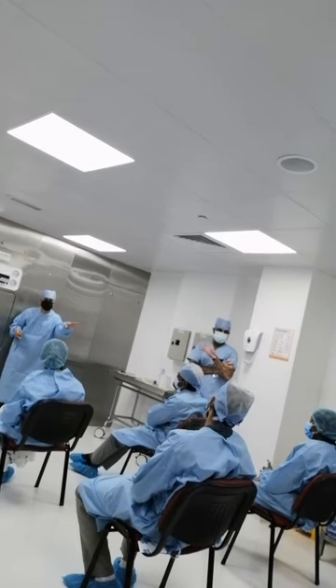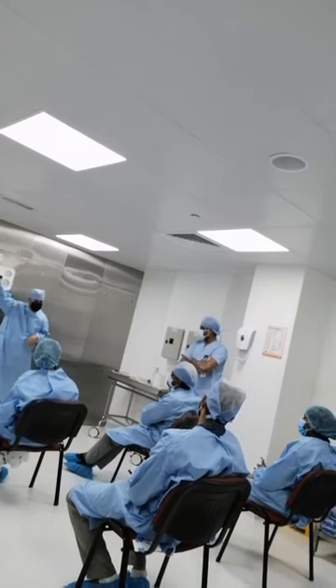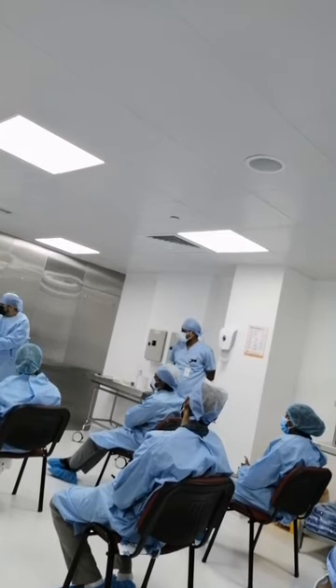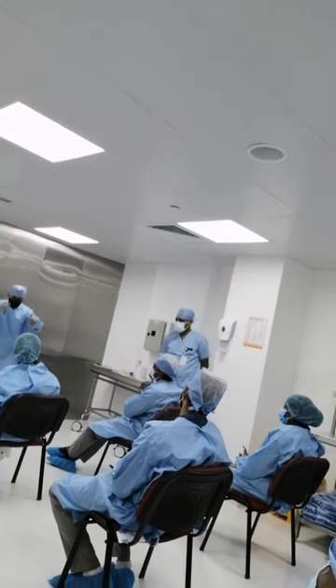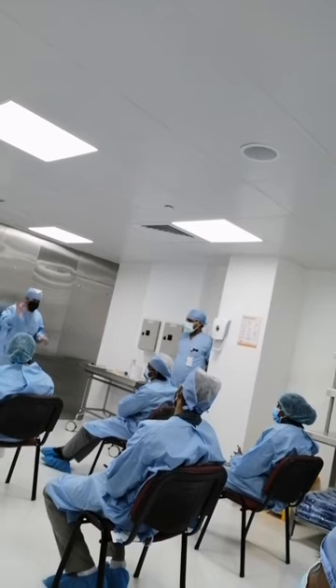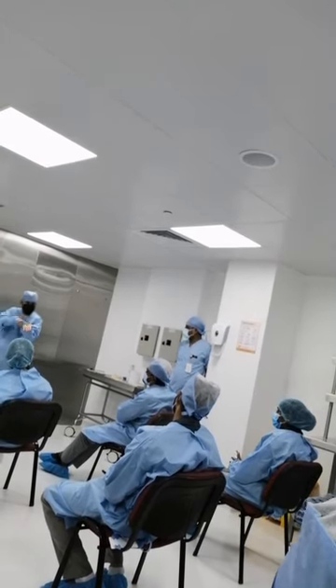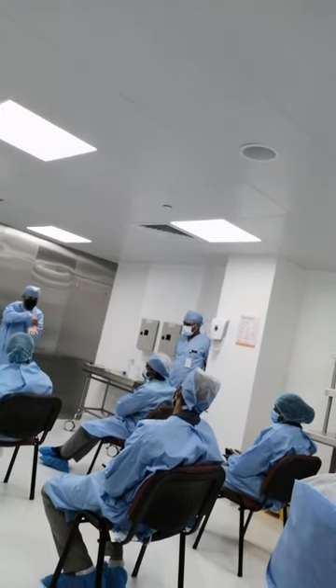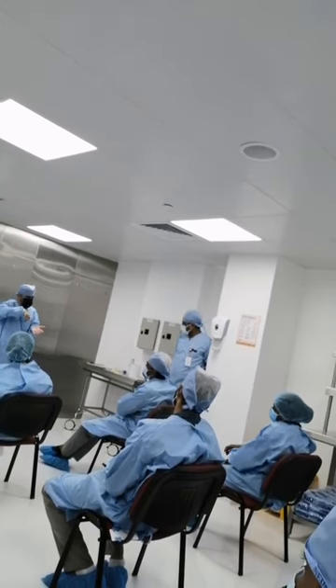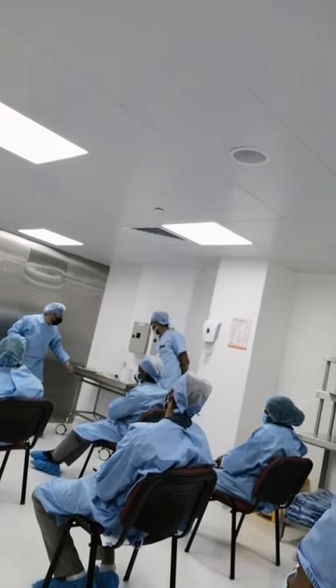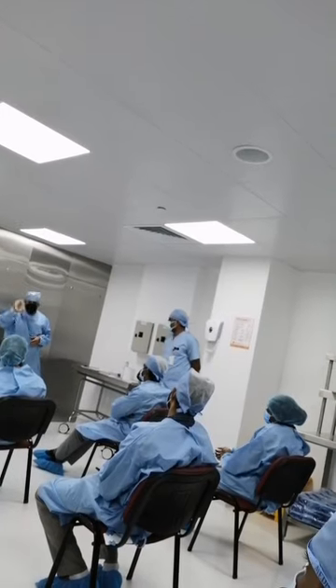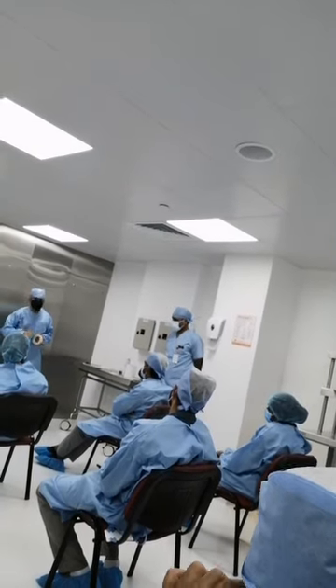If you find it in the Middle East, you will find somebody from the oil and gas section, and they will come and put some kind of sensors inside the machine, and they will tell you it is okay. No, we are not doing this. We get your instruments and put thermocouples on the instruments. Okay, and sometimes this test will tell you, I'm sorry, this instrument cannot be sterilized. Exactly. Throw it. It cannot be sterilized.